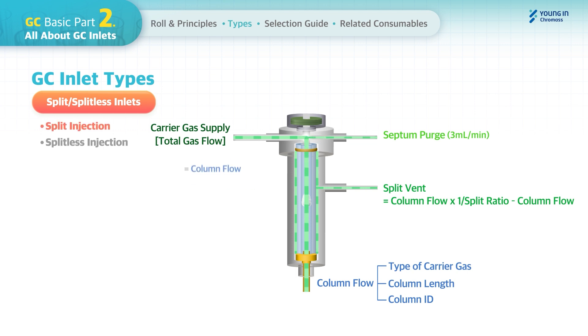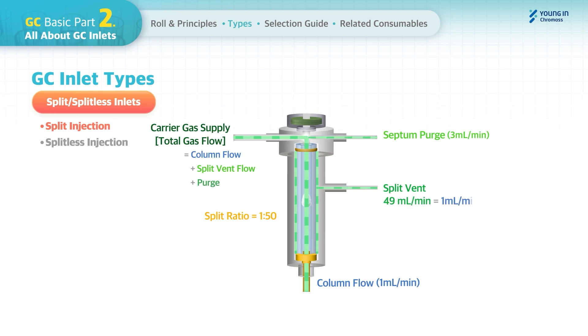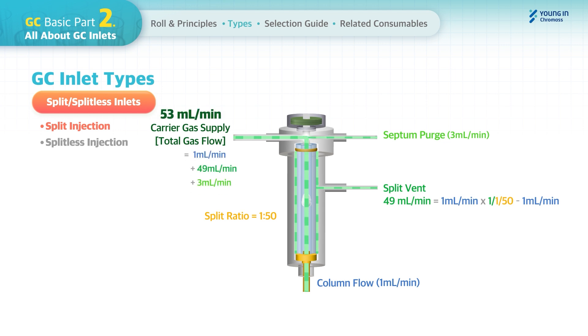In the split injection mode, total gas flow is set as follows: for example, if you set the column flow at 1 mL/min and the split ratio is 1:50, the split vent flow will be calculated at 49 mL/min. The total gas flow is set accordingly, and after the gas flow stabilizes, the sample is injected.